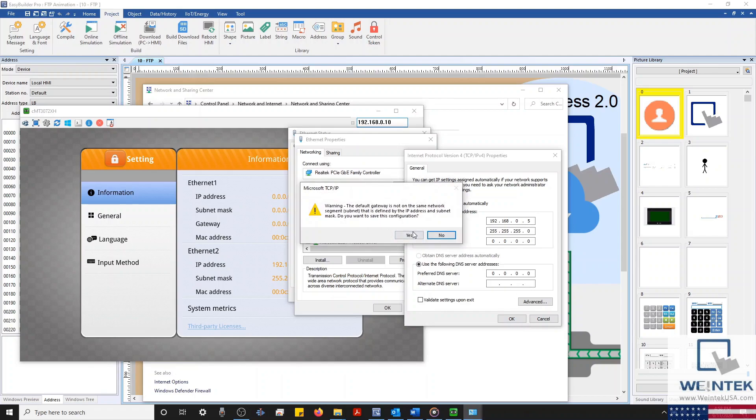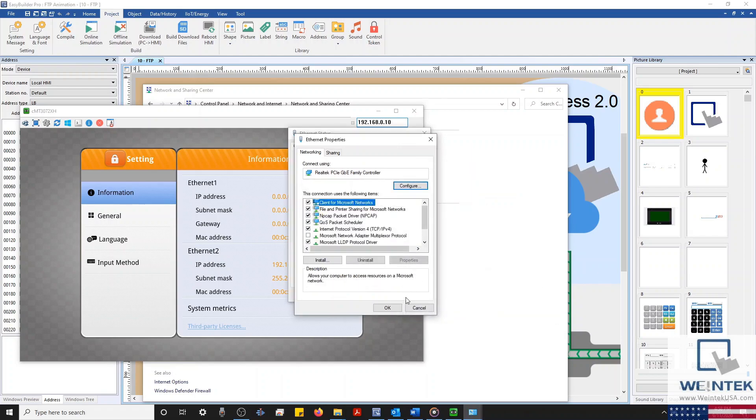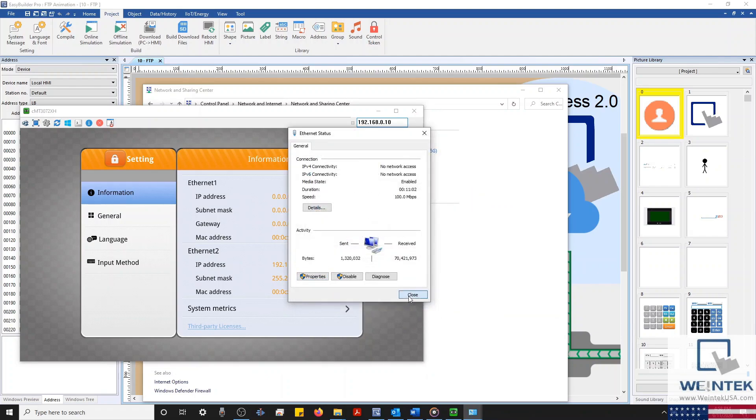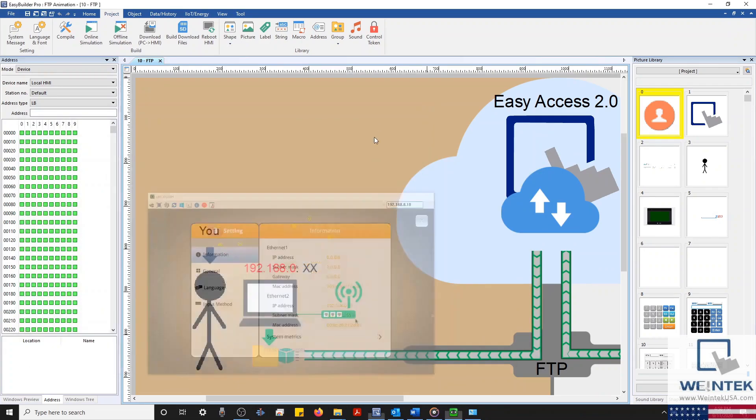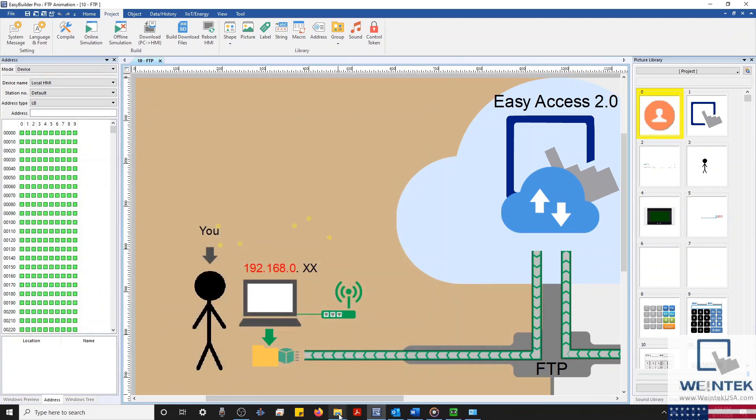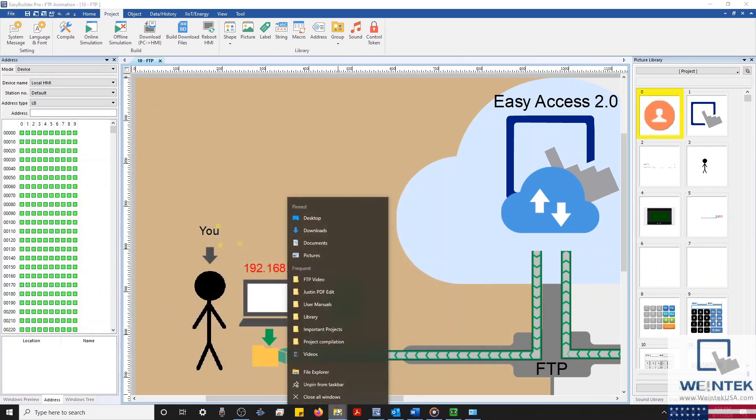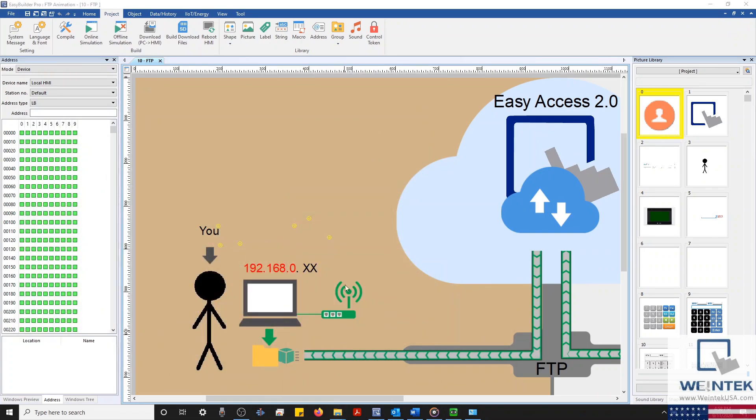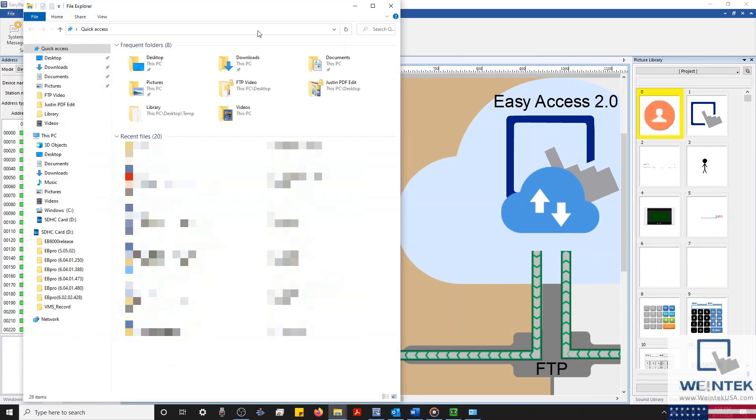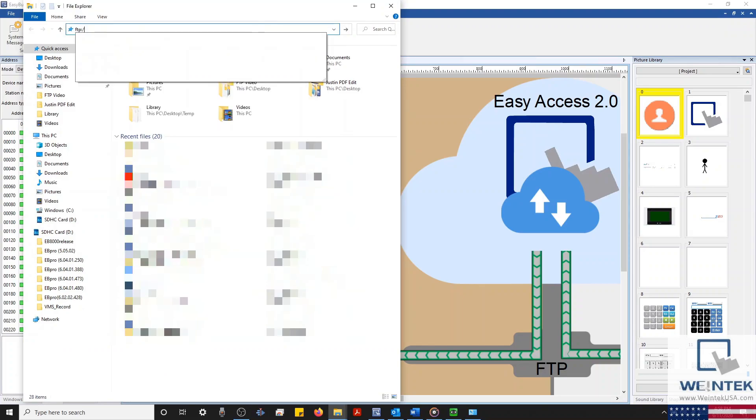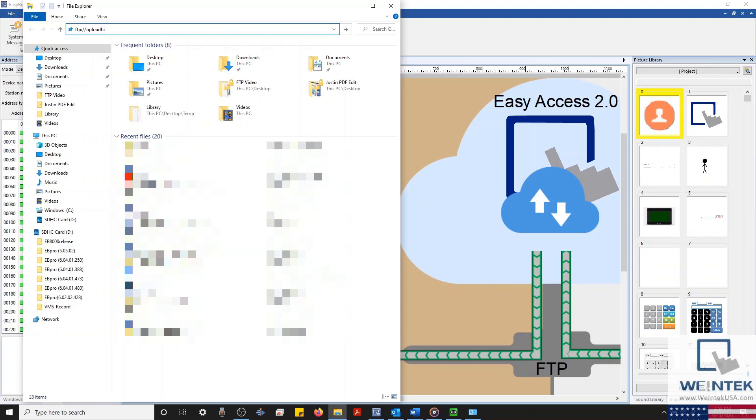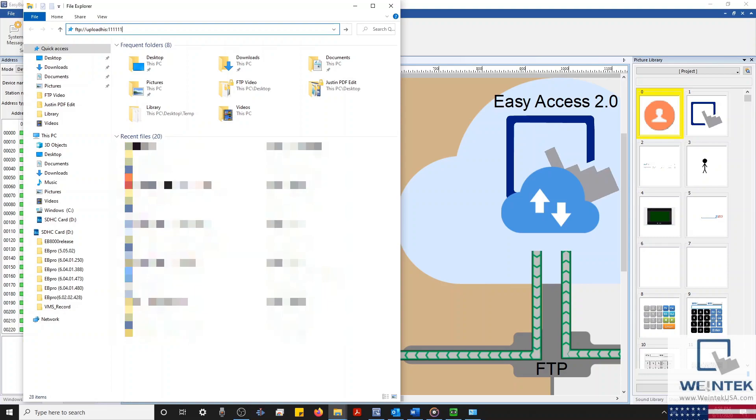Now, we should be able to access our HMI's internal and external memory. Let's open our file browser and enter the address of our FTP server. Currently, our HMI is configured with a default password of six ones, and then I'll type at, followed by our HMI's IP address, which is 192.168.0.10.